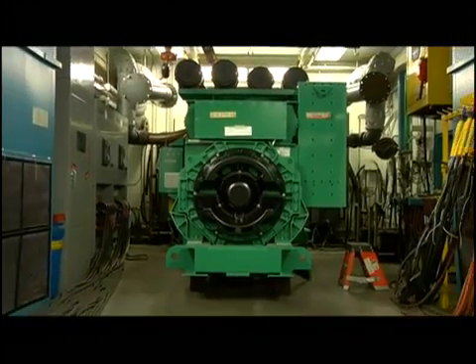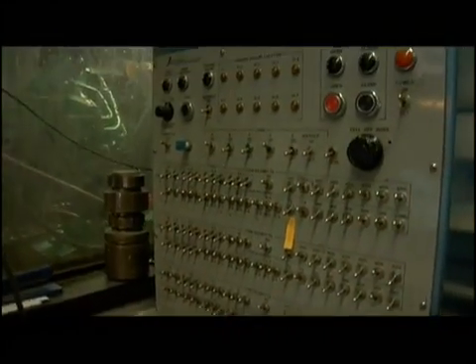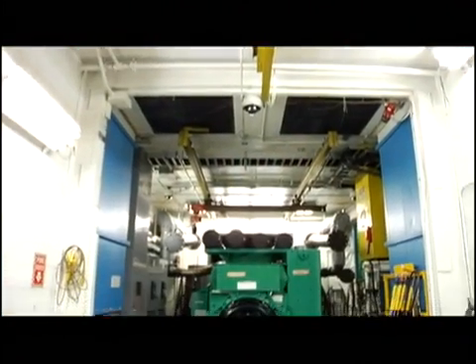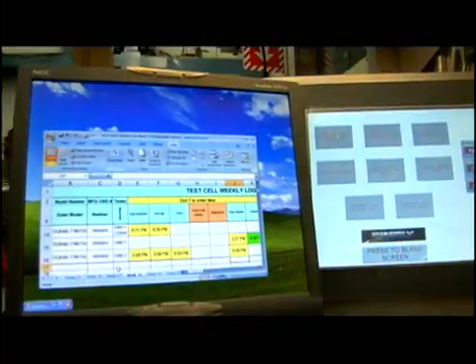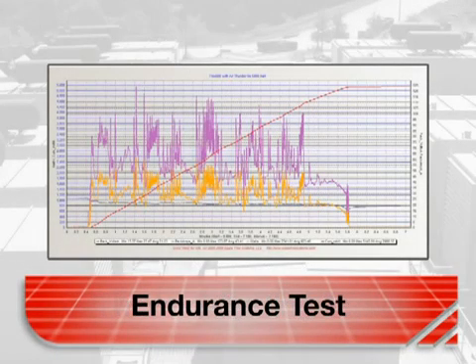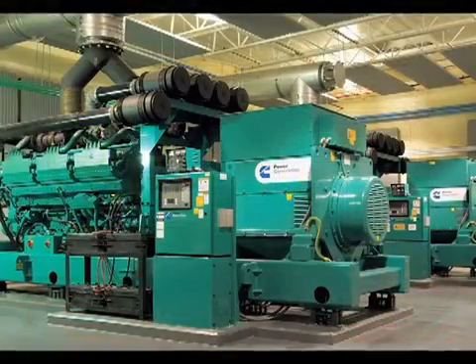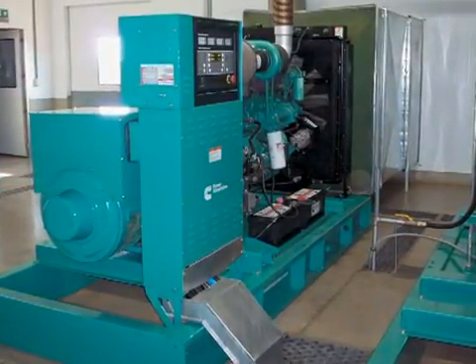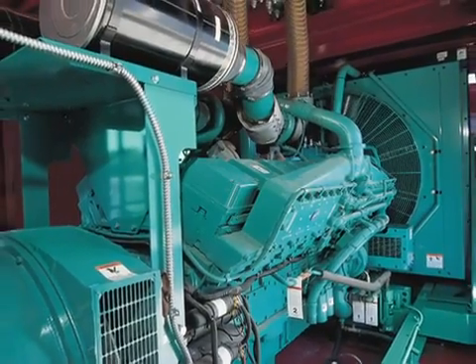It is much better to have an engine and radiator designed and tested to work together. That's why there is great value in the kind of well-documented factory testing that Cummins does. Such testing simulates the air flow in a typical power room and uses dedicated instruments to measure the ambient temperature at various points. Two other kinds of tests are also valuable: a thermal cycle test, which evaluates radiator cores for resistance to mechanical stresses by alternating hot and cold environments, and an endurance test, which runs the system for an extended period of time to estimate its lifespan. There is no better alternative to a tried and tested system coming straight from the factory, as a do-it-yourself approach to cooling systems can bring unknown risks and problems.